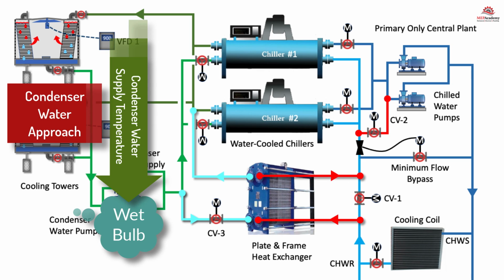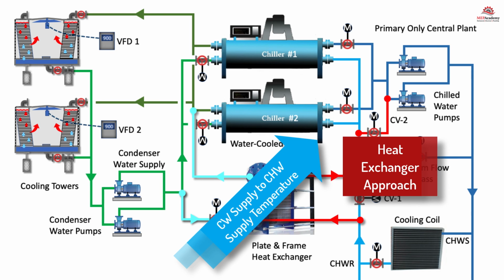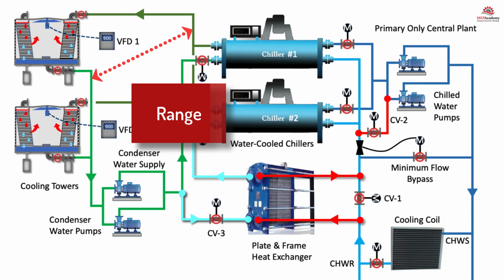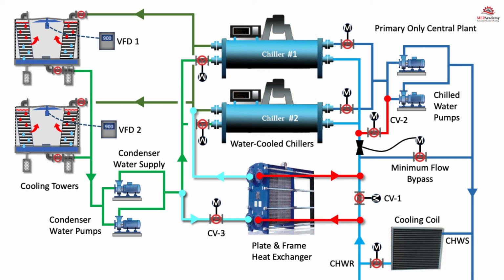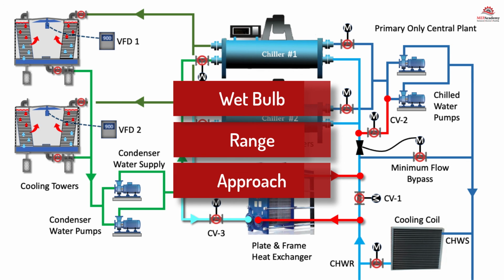There is the cooling tower or condenser water approach that defines the condenser water supply temperature in relationship to how close it gets to the ambient wet bulb temperature. Then there is the heat exchanger approach that compares the condenser water supply temperature to the chilled water supply temperature across the heat exchanger. Another important value would be the temperature range of the condenser water. That's the difference between the condenser water return minus the condenser water supply. The three important factors in sizing the waterside economizer are the wet bulb temperature, the temperature range, and the approach.